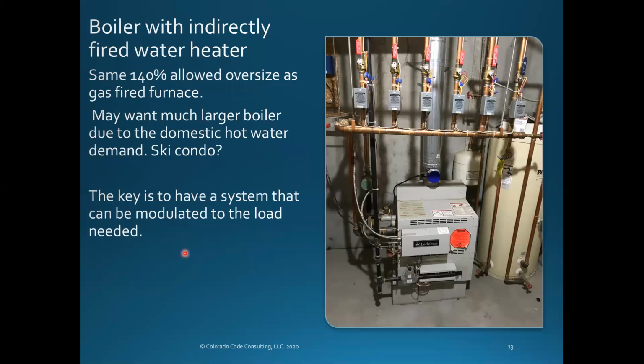The key here is I might have a condo that needs an 80,000 BTU boiler, but they've got indirectly fired water heaters. They might have 3 or 4 of these in a ski lodge, but I don't need a lousy 80,000. I need about 350,000 BTUs just to heat that up, because everybody goes skiing, right? And then they all come back and want to take showers at the same time before they head out in town, right? So there's a different expectation, a different real life there.